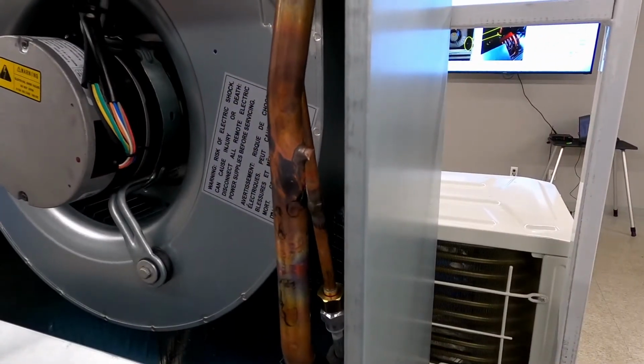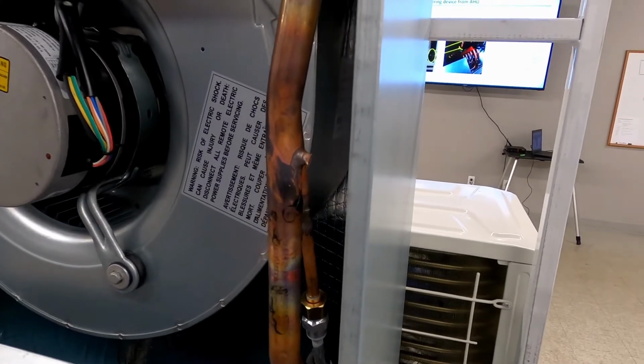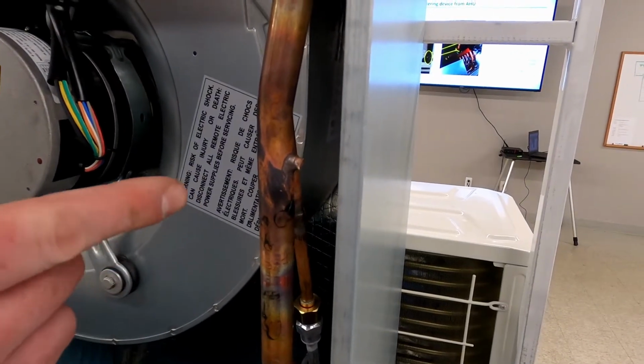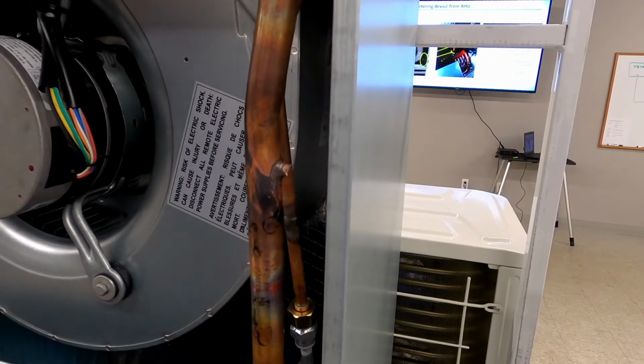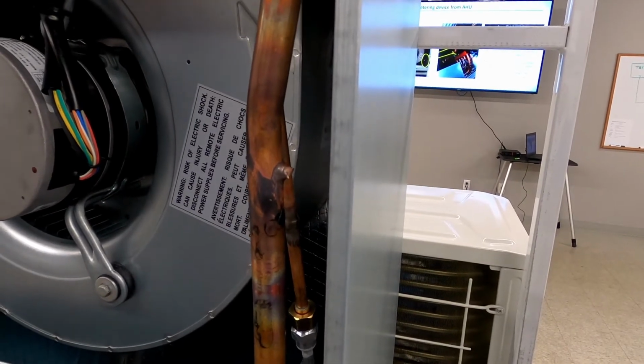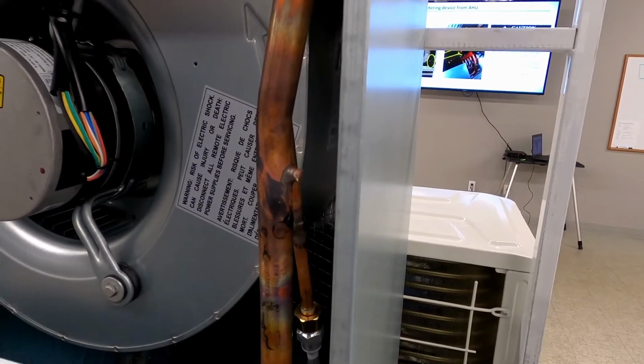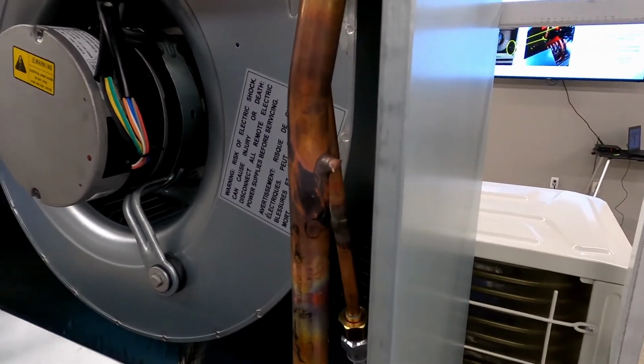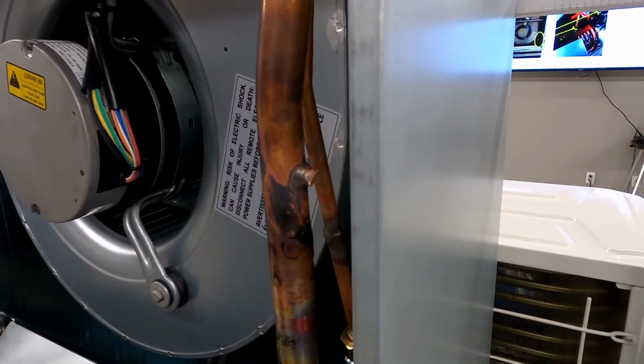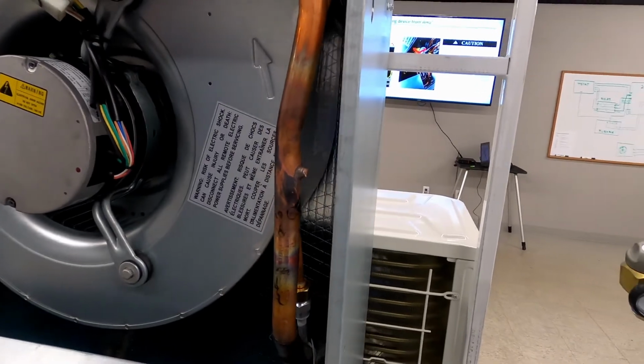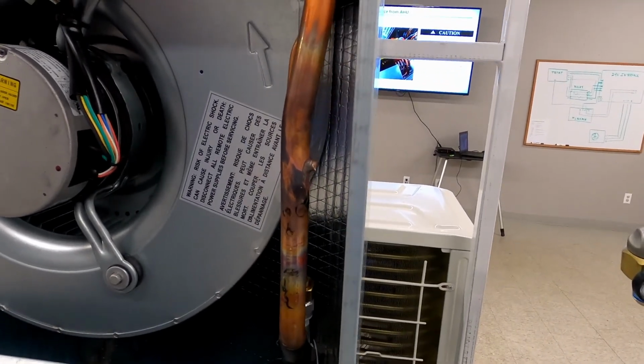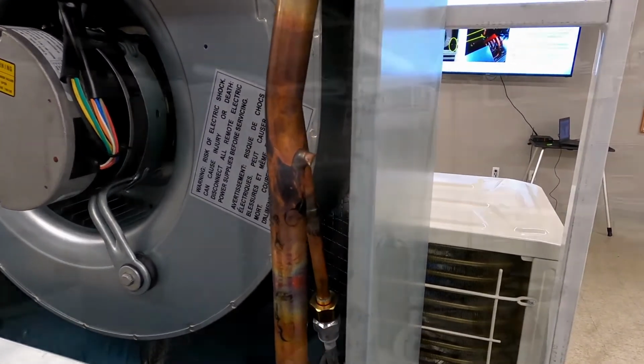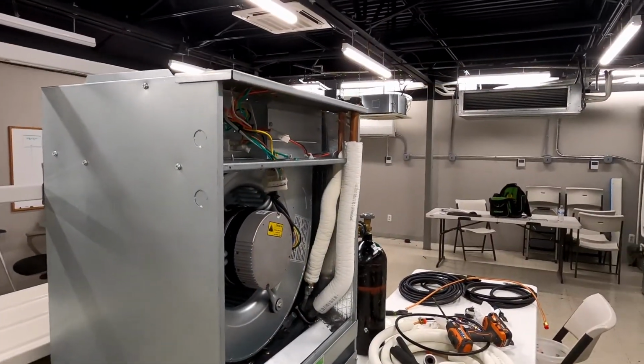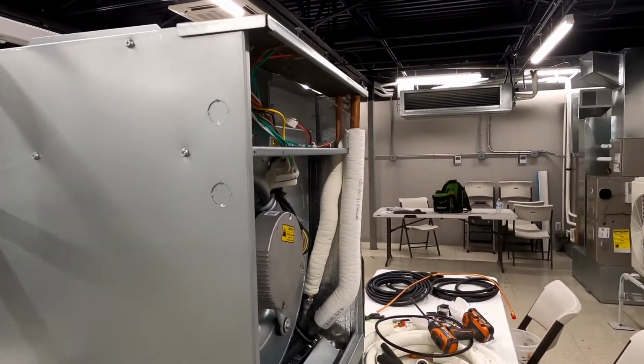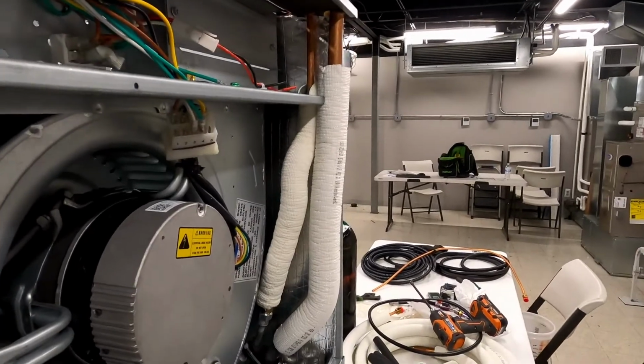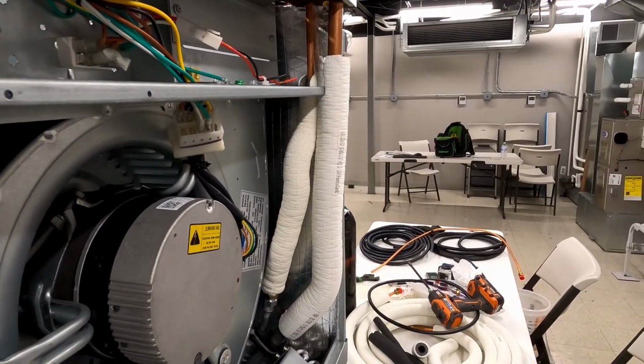Now that we have our liquid line connected, now we need to braze shut our TXV equalizer line in the suction line. It's important whenever you're doing any brazing in the system that you have nitrogen flowing, especially with the ductless combination, because the ductless outdoor unit has very fine screens at the expansion valve. After you remove the expansion valve, it's important that you replace the insulation on the lines inside the cabinet so that you don't have any condensation that drips where it shouldn't be.